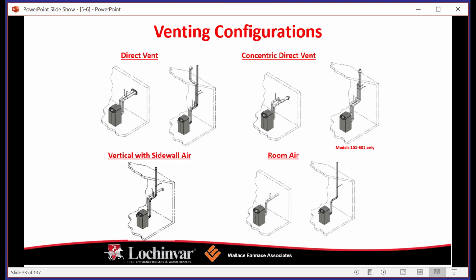Venting configurations. This is a good slide that shows a little bit of everything that you can do, again showing the forgivingness of the condensing boiler. In the upper left-hand corner, you can see direct vent, where we have a fresh air intake for our combustion air, and our flue gases are exhausted through the main plane in the side of the building. You can go right out the side, or out through the roof penetration. Flat roof, doesn't matter.